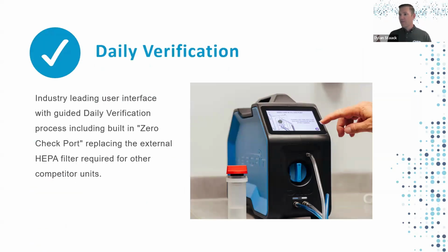So daily verification, we talked about the industry-leading interface on our daily verification. We have that zero check, that HEPA zero port right on the front there. I talked about it. Now you can see it. That clear line is attached to it up to the right of the wick there. That has completely replaced the need for an external HEPA filter. It's one less thing you have to worry about losing, breaking, buying again.